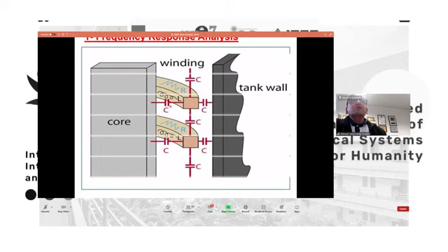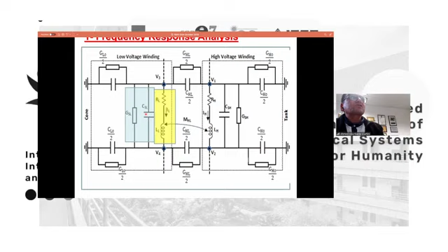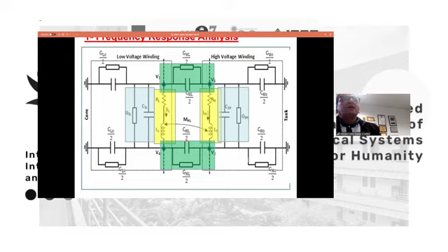We start with the low voltage winding, which can be represented by series inductive elements, R and L. Because this winding has insulation paper between turns, the insulation paper can be simulated as a dielectric capacitor shunted by dielectric conductance. Similarly, we have the high voltage winding, represented by inductive elements shunted by dielectric capacitance and conductance. In a transformer, we have first the core, then the low voltage winding, then paper insulation and oil, and then the high voltage winding. So between the low voltage and high voltage windings, we have mainly paper insulation, and oil going in ducts, which can be represented by capacitors and conductors. Between the low voltage winding and the core, when we wind the transformer, we start with the core, then the low voltage winding.